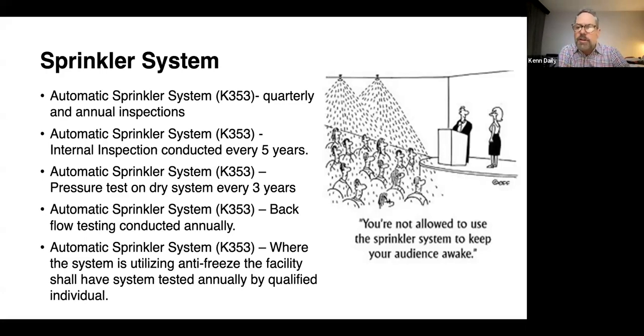Again, it's looking for material, water buildup, and or rust, dirt, corrosion, or microbiologically induced corrosion, which is called MIC. And then you would have a dry system test. If you have a dry system, you have a pressure test. They kind of pump your system up to 40 pounds, turn off the compressor, and see what happens over the next couple of hours. If you lose more than 3 pounds of pressure, you're non-compliant. You need to be looking for pinholes.